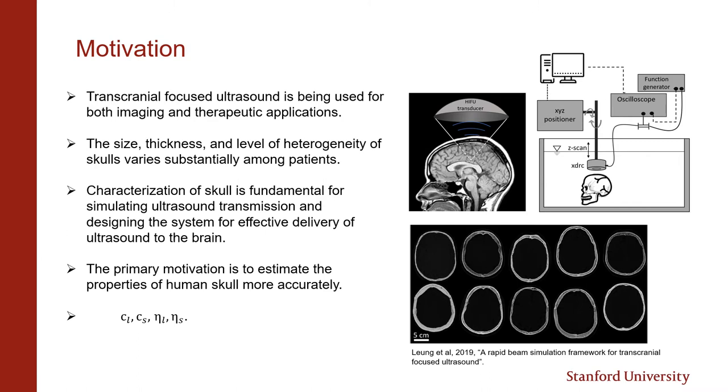Presence of a skull in non-invasive transcranial focused ultrasound distorts the ultrasound beam depending on the acoustic characteristics of the skull. The size, thickness, and level of heterogeneity of a skull varies substantially among patients and even at different spots on the same skull. Therefore, an in-situ characterization of a skull is fundamental for simulating ultrasound transmission and designing the system for effective delivery of ultrasound to the brain.